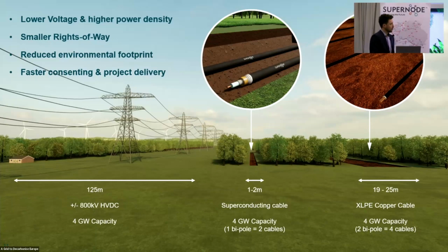The takeaway from this slide is all about consentability. We know some of the high capacity cable projects in Europe, for example the SuedLink project, its main challenge isn't really technical, it's consenting, it's timeline. With a superconducting cable, because you can operate the system at lower voltage and at much higher power density, it can be much more compact. You have smaller rights of way, reduced environmental footprint, not just on the cable itself but on all the auxiliary and connecting equipment. And it makes it much more acceptable to the public and much quicker to roll out for a transmission system.